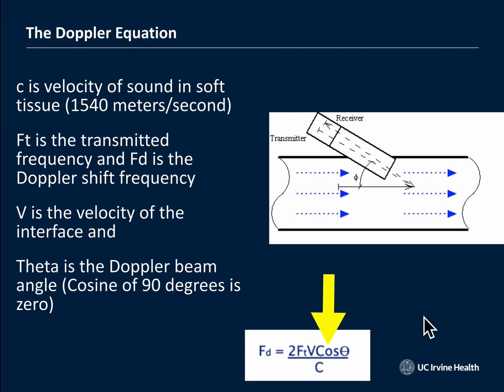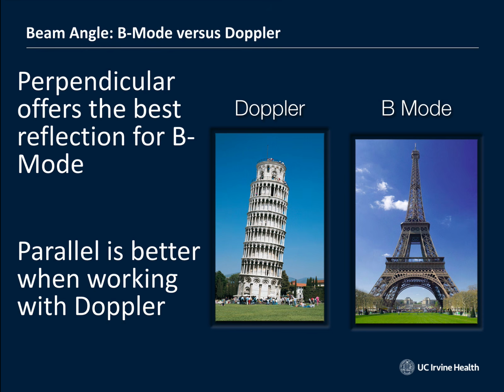Does anybody know what cosine of 90 degrees is? Good, it's 0. It's right here on my slide. So that's why Doppler works much better as a more parallel plane, because once this theta gets all the way up to 90 degrees, the angle of inclination between the probe and the flow, the Doppler is not accurate. So you really want to be more parallel than perpendicular when it comes to Doppler.